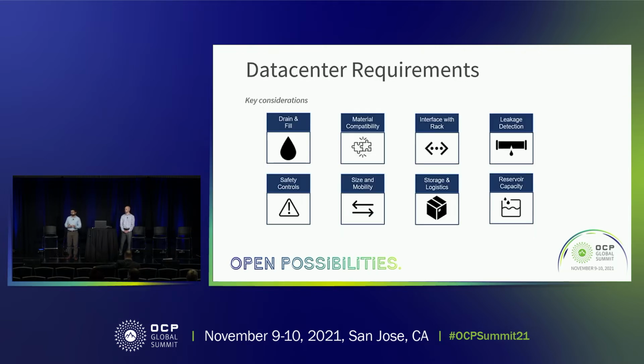Before we dive into the details of the design and capabilities, let's take a quick look at the data center side of things. First and foremost is drain and fill. If liquid cooling hardware fails in the data center, like a liquid cooling rack, the mobile service cart should be able to purge all the liquid out and then fill it with fresh coolant on the replaced hardware.